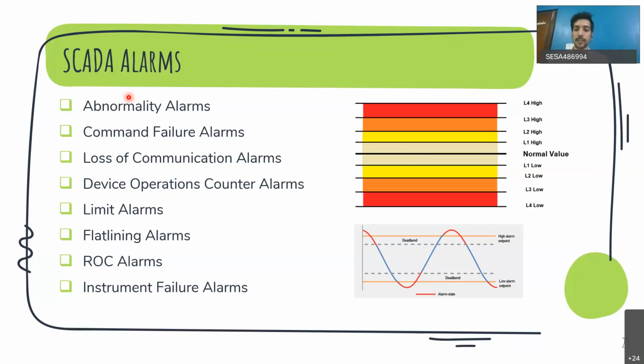Similarly, limit alarms. You can configure limits for your voltage and current or any analog data. So whenever values are crossing those limits, above or below, limit alarms will get generated. Flatlining alarm means generally some values should not be constant. They should always keep changing. But for example, if any value is constant for some time, this alarm will get generated. Then rate of change alarm. Some values should not change too drastically.